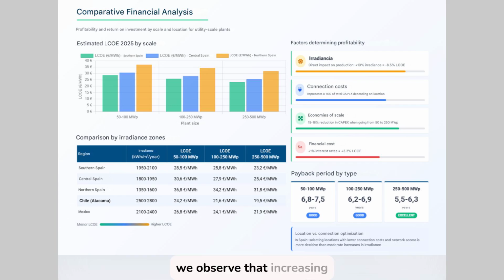In all cases, we observe that increasing capacity consistently reduces the LCOE, a €4 to €6 reduction when going from 50 to 250 MWp. This is due to both economies of scale and the dilution of fixed costs. The table below adds global context with data from Chile and Mexico. Atacama, Chile, the most competitive region in the analysis, with an LCOE of just €19.5/MWh for large plants. Mexico, also very competitive, between €21.90 and €26.8/MWh. This demonstrates how irradiance is the dominant factor when it exceeds 2,100–2,500 kWh/m2/year. In contrast, regions in northern Spain or Central Europe with irradiance below 1,600 have a much higher LCOE, even for large PV plants.